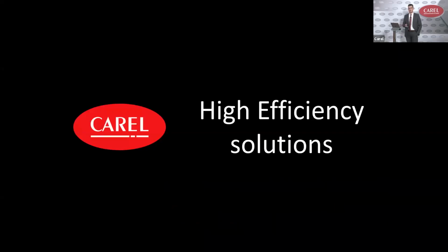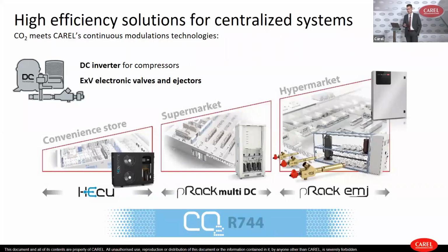Okay, so now it is time to speak about our high efficiency solutions for CO2 condensing unit racks. In CAREL, when we speak about high efficiency, we speak about continuous modulation. So what does continuous modulation mean? It means that in your rack, there are some devices able to modulate with a wide range of modulation and match perfectly the load conditions required by the evaporators, by the cabinets, by the users of this cooling capacity. And these devices are, of course, DC inverter compressors, but also electronic expansion valves and electronic modulating ejectors for transcritical CO2 racks.